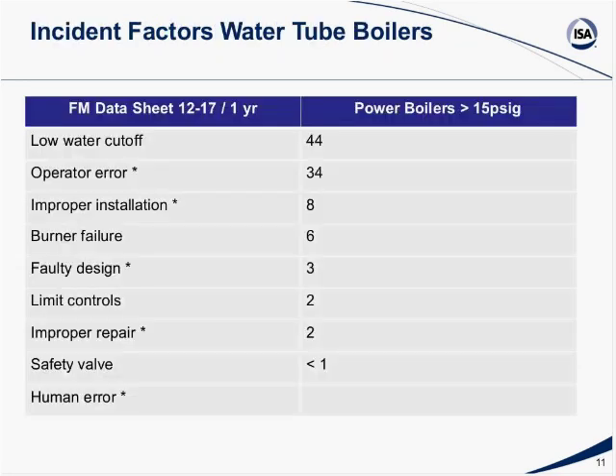These next slides talk a little bit about some of the reasons that this particular insurance company had input and had to pay for repairs. You'll note I've asterisked a number of the items. These represent pure human error or interface problems. Low water cutoff was by far the most, with 44. That is, people did not shut the boiler down when the water got low, which would eventually cause rupture of tubes or other damage to the system. Operator error, there were 34 incidents reported to the insurance company.